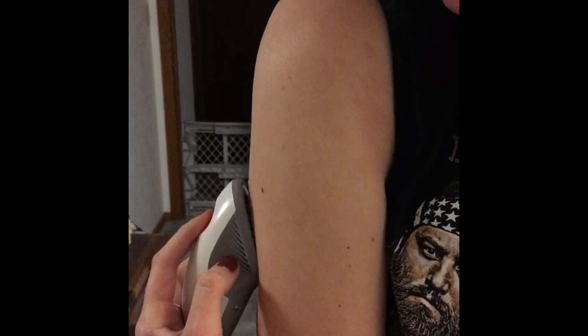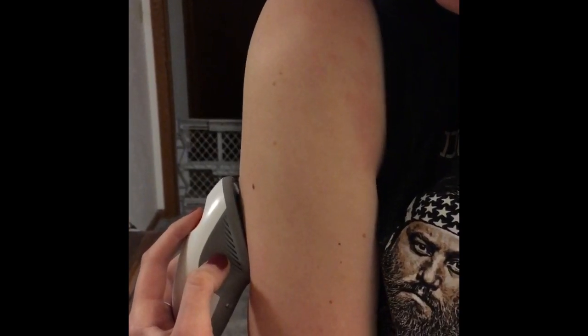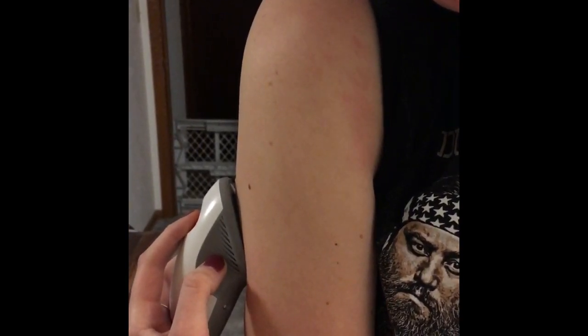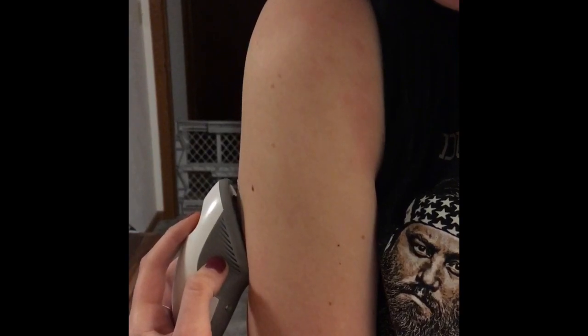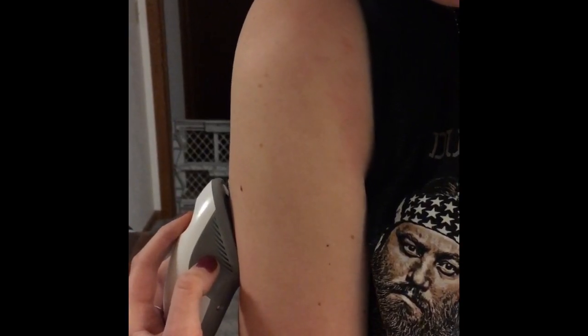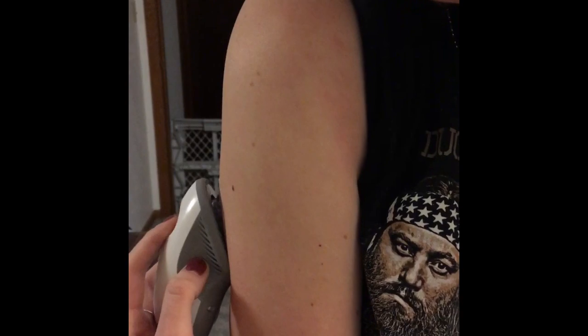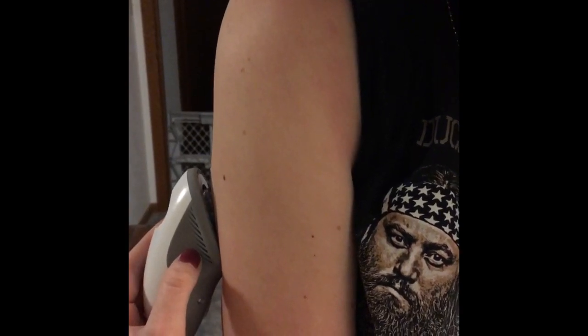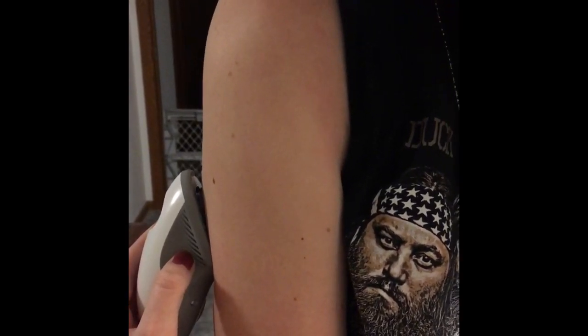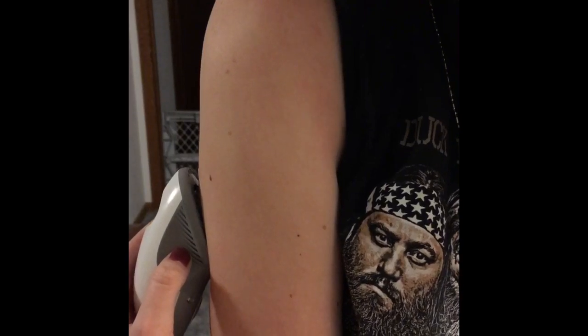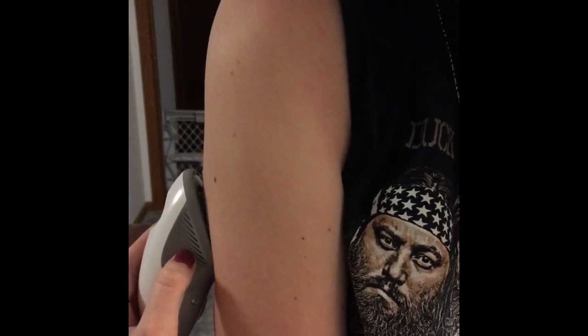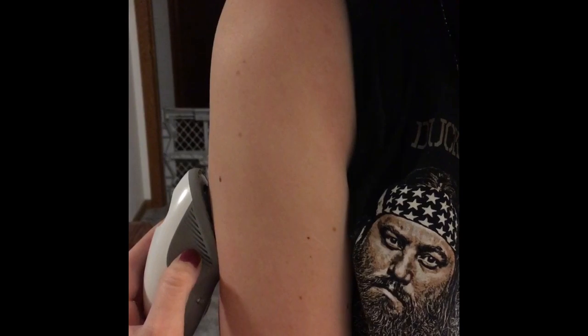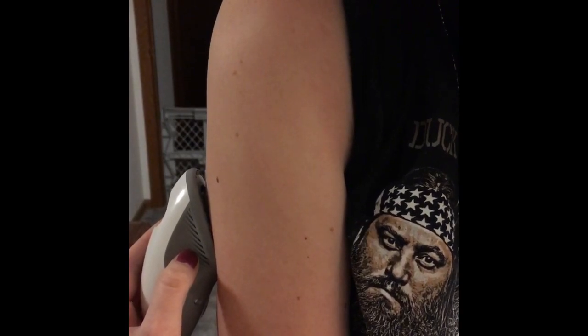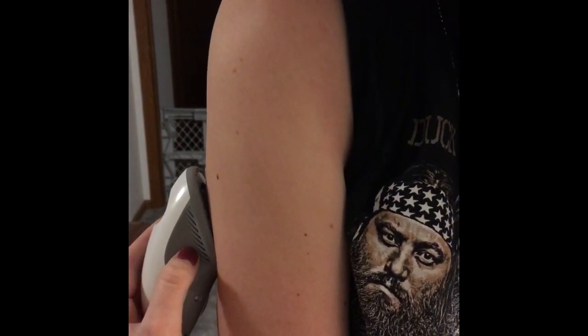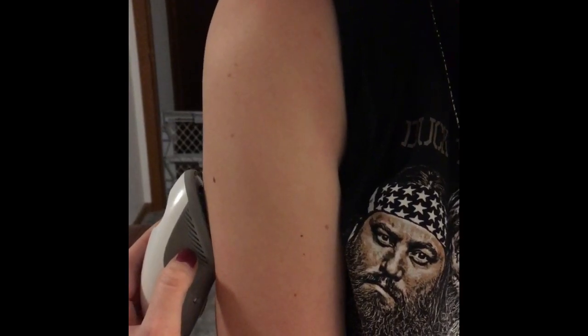Here you can see me inserting the sensor on my arm. However, I did not put it completely flush against my body, but it did work. The part that wasn't flush was not where the needle comes out, but please be cautious and make sure it is completely flush against your body. This sensor ended up having a problem anyway -- 9 hours later it gave me a calibration error, and I had to call Dexcom and they had to replace it. But make sure it's flush against your body regardless; that's not the reason this sensor failed. It failed because there was something wrong with it from manufacturing.